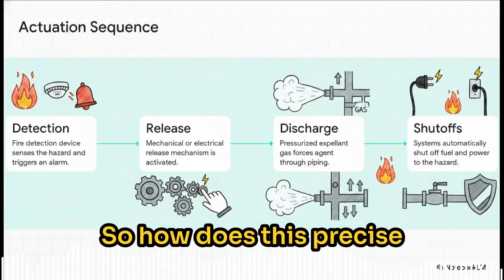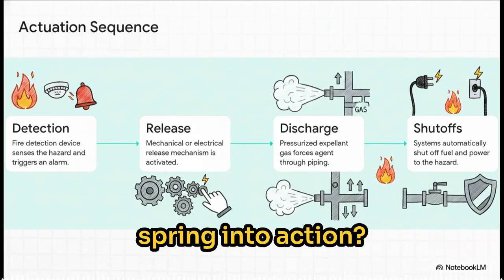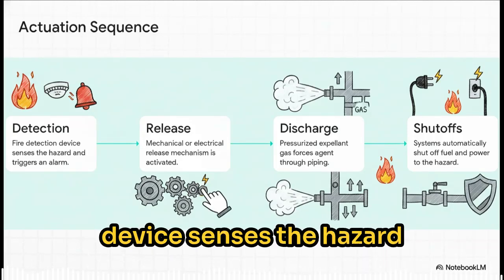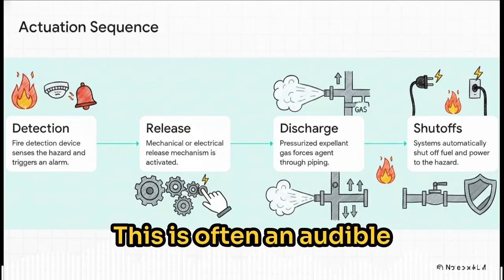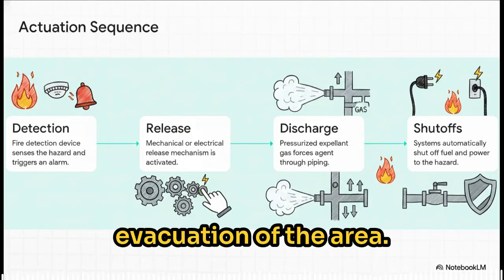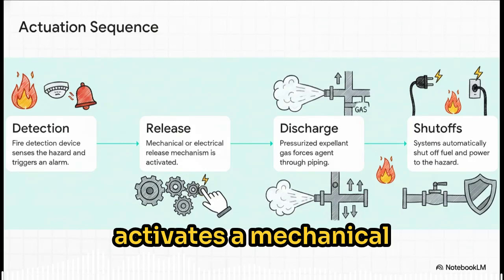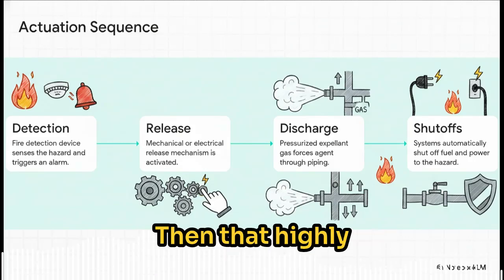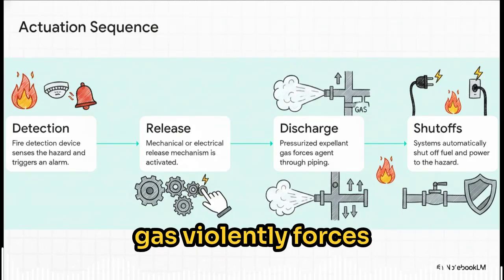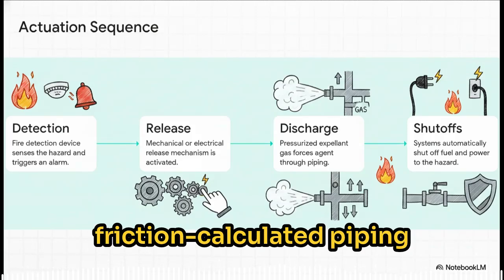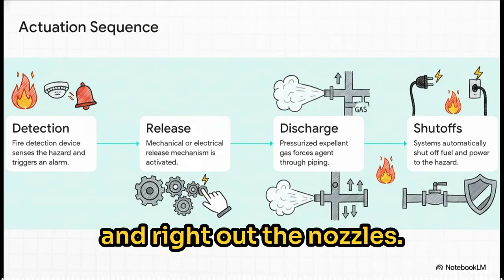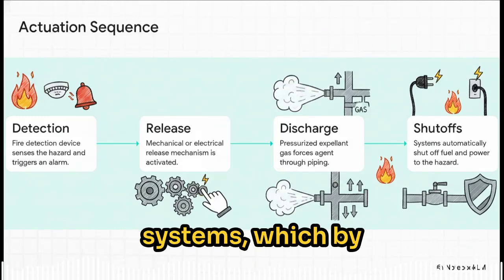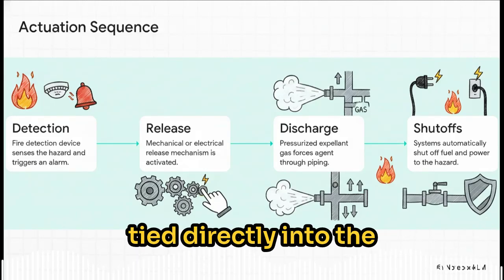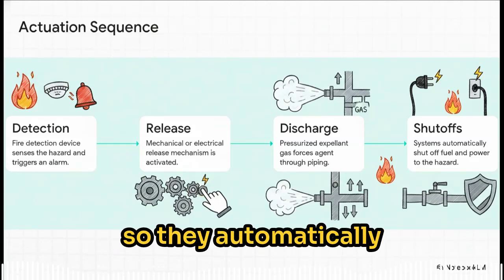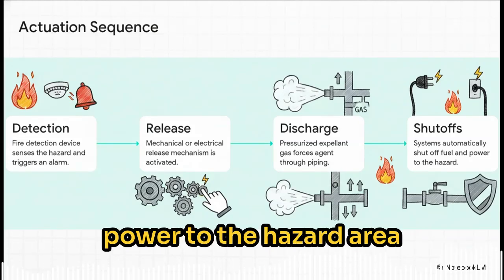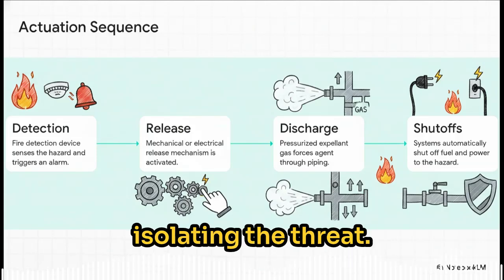So how does this precise machinery actually spring into action? Well, first, a fire detection device senses the hazard and triggers an alarm. This is often an audible warning signal to facilitate prompt evacuation of the area. This immediately activates a mechanical or electrical release mechanism. Then, that highly pressurized expellant gas violently forces the dry chemical agent through that friction-calculated piping and right out the nozzles. Crucially, the vast majority of these fixed systems, which, by the way, can also be triggered manually, are tied directly into the building's infrastructure, so they automatically shut off the fuel and power to the hazard area the very moment they actuate, completely isolating the threat.